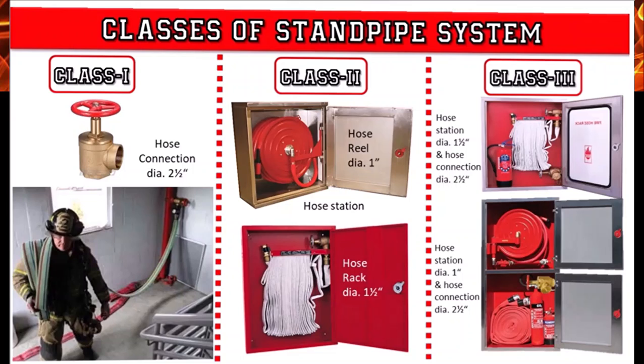Some later versions feature both a 2.5 inch firefighter connection in addition to a separate 1.5 inch connection attached to an on-site installed hose. Finally, there are versions of Class 3 systems that feature a 2.5 connection, a reducer to a 1.5 connection, and no installed hose. So that is the summary of the classes of standpipe system.